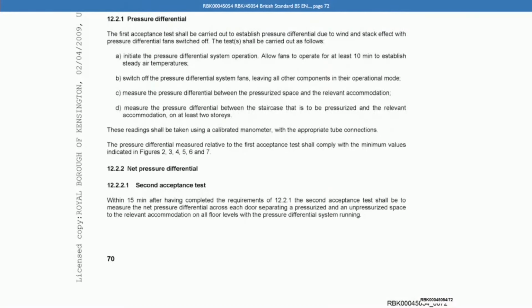I think if we go back a page and look at the first part of what it said. Across each door, separating a pressurised and unpressurised space on all floor levels with the pressure differential system running. Now, I think you've explained that you just did it on a sample number of floors. Is that correct? The pressure differential, the initial test with the fans off, dampers open, we did on at least 4 levels, starting at lower level, a quarter of the way up, three quarters of the way up and top. The second acceptance test, which admittedly we didn't do after 15 minutes because we couldn't at the time because not all floors were available. Yes.